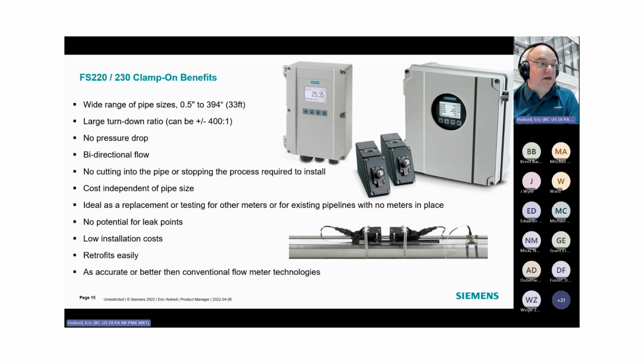Any of these systems in liquid flow can handle pipes from half an inch up to about 33 feet in diameter. So huge penstock types of pipes. The turndown ratio is about 400 to 1. The system offers zero pressure drop. Flow can go backwards or forwards, and the totalizer can be set up to do flow all in one direction, flow in both directions, or a net flow type of setup.